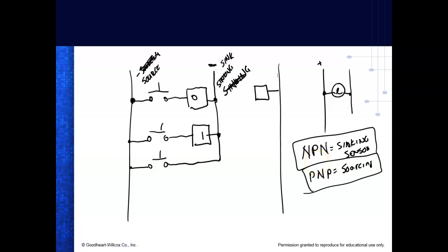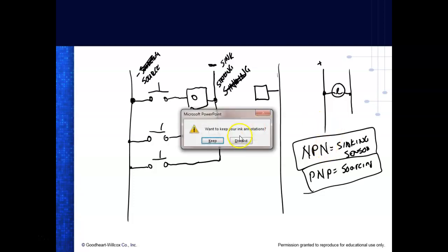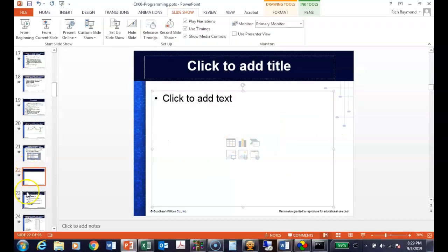So some PLCs give you the ability to configure whether it's for sinking or sourcing. Some PLCs, that's fixed. Allen Bradley has a tendency on their PLCs to let you decide, unless you get a modular PLC. So with a modular PLC, you're either going to buy sinking inputs, right? So this guy's got sinking inputs, and it's got sourcing output modules. But you could buy a module that's opposite, right? You understand? So it all depends basically on where you work and what they decide to use.